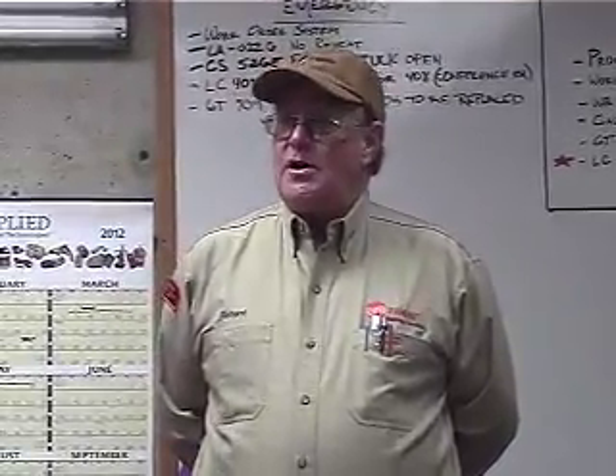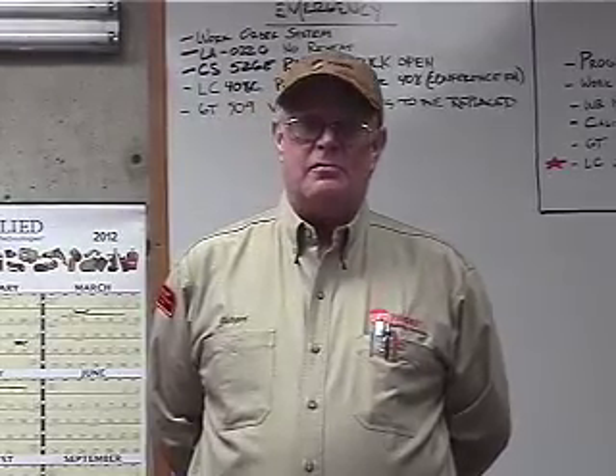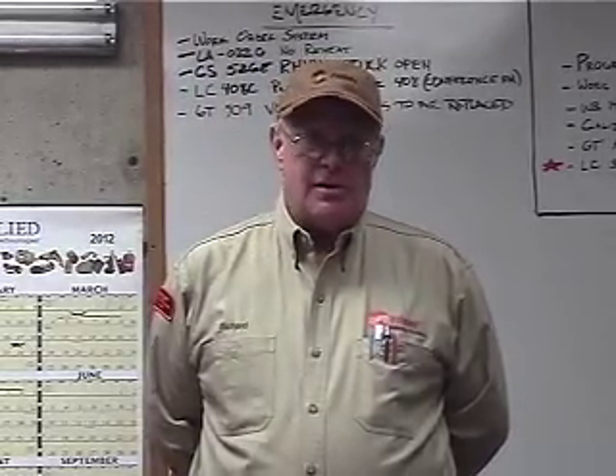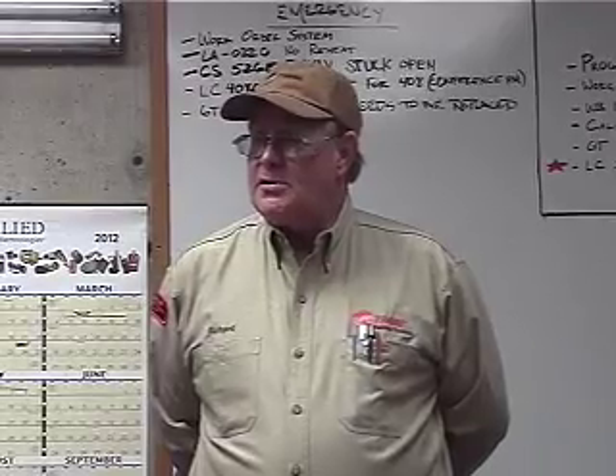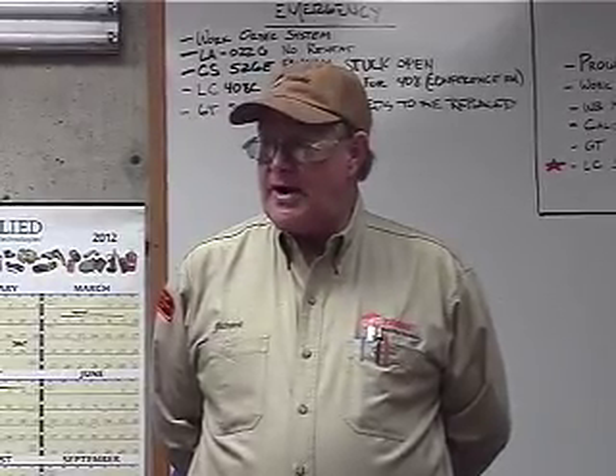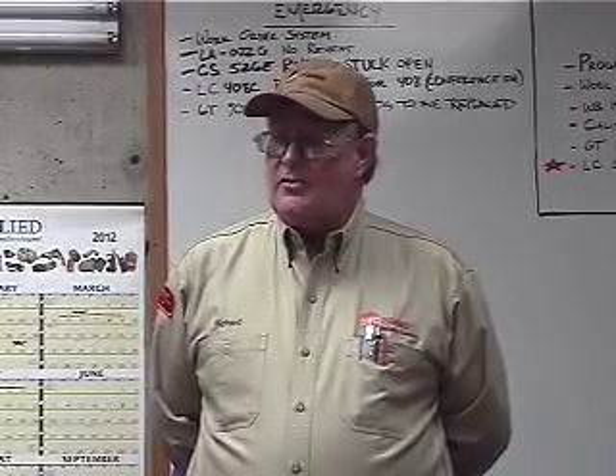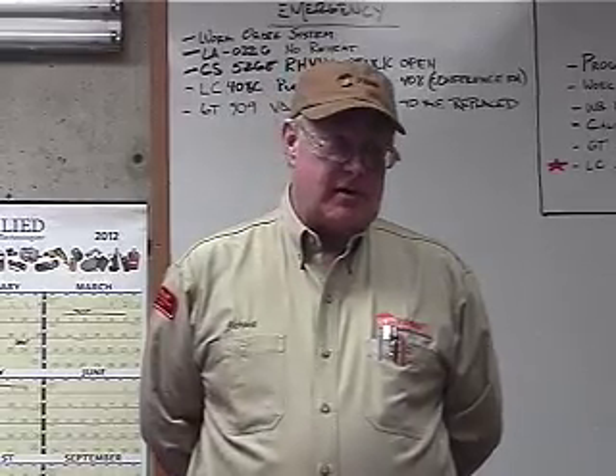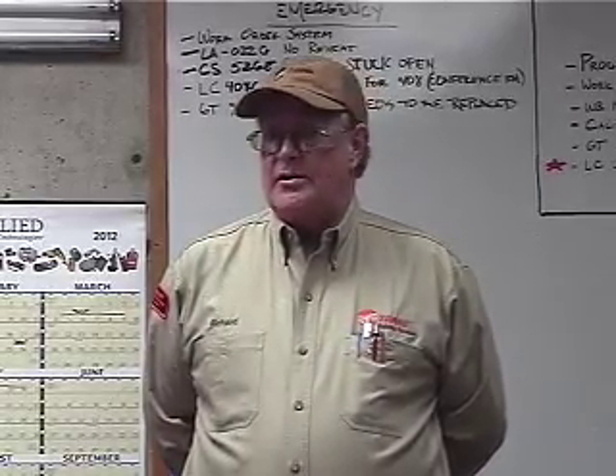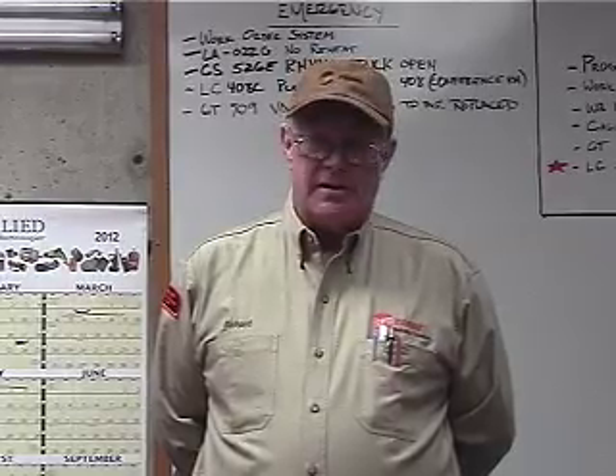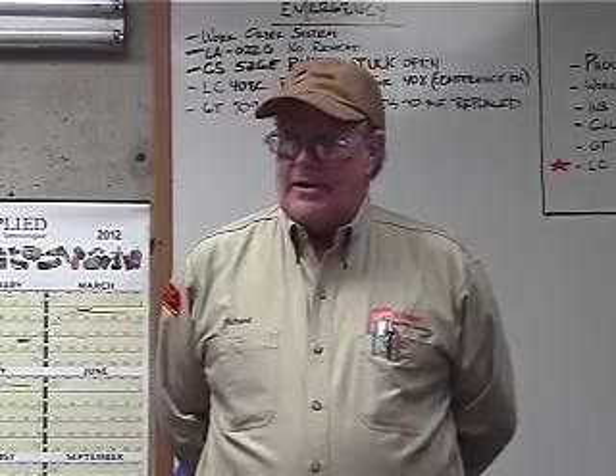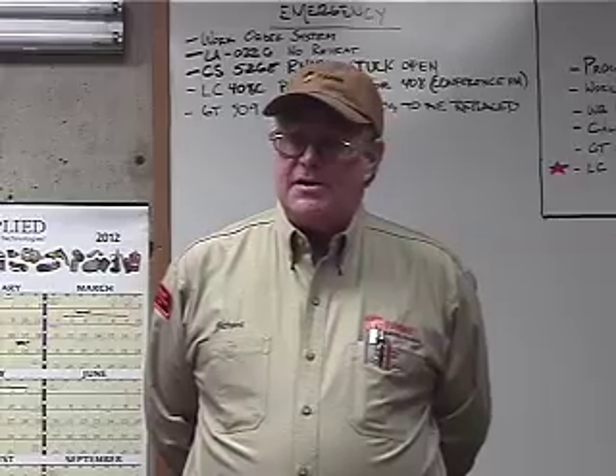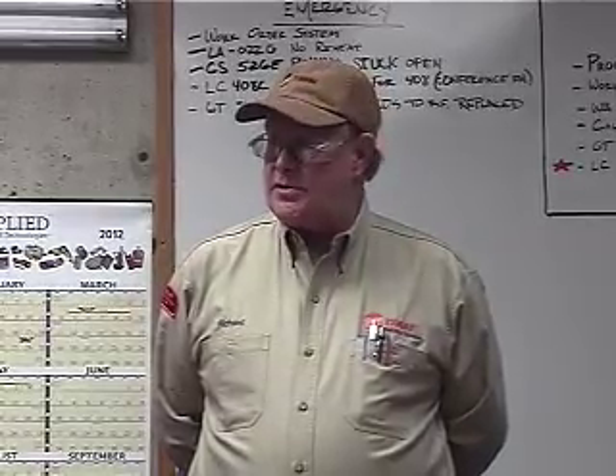Some of the main problems that you may run into are going to be water flow issues. If the water flow is going too slow or too fast, the faster the water flows, the less heat it's going to pick up. If it's slowed down a little bit, it's going to pick up more heat and reject it out. The main thing that I've seen around here has been water flow issues in the past.